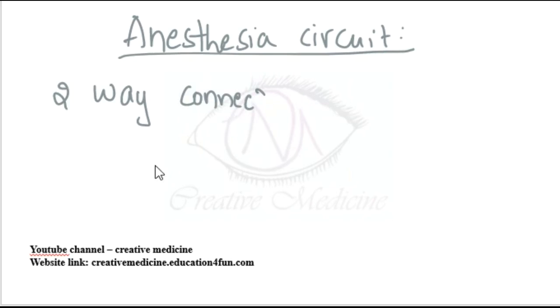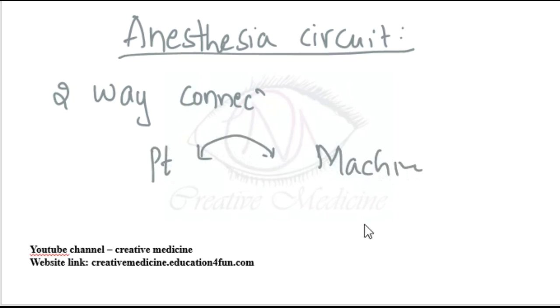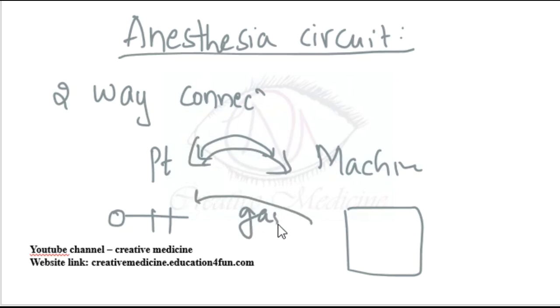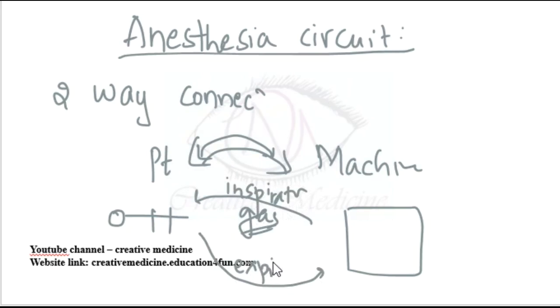We have learned about the anesthesia machine in the last class. We have an anesthesia machine and we also have the patient. The connection between this anesthesia machine and the patient is called the anesthesia circuit. This circuit will bring inspiratory gas towards the patient and will also take expiratory gas away from the patient into the machine or to the outside.